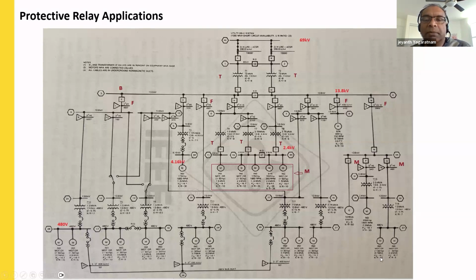And also you get the low voltage buses as well in order to feed the low voltage motors and other auxiliary applications. So when it comes to the protection, there are motors. Motors need to be protected by motor protection relays because motors require dedicated protections. When it comes to the feeders, the feeder protection relays are being used to provide protection for the feeders, technical cables and the conductors. And when it comes to the transformers and the bus, those devices require differential protection. Then the bus differential and the transformer differential protections are being used to provide the required protection for those devices.